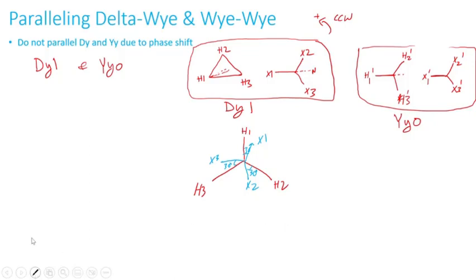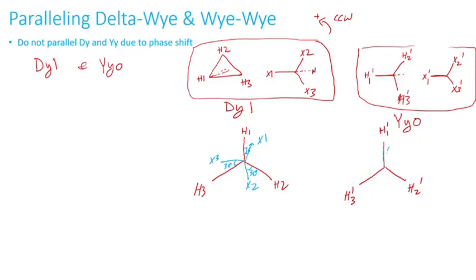Now let's do the same for the yy transformer. I'll draw the high side: H1 prime, H2 prime, H3 prime. Since there is no phase shift, X1 prime aligns with H1 prime, X2 prime and X3 prime are in parallel with the high side. For clarity I'm using arrows — the phase shift is zero, so the phasors are exactly in parallel.